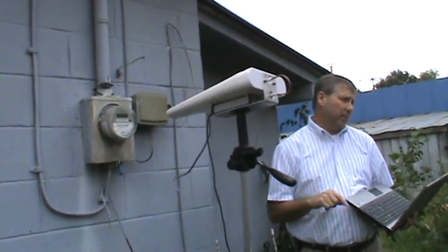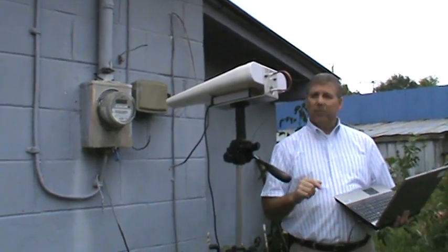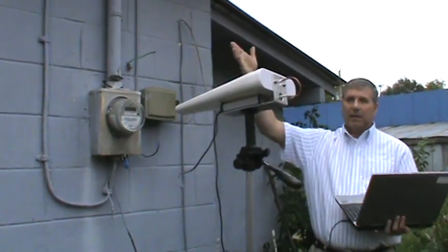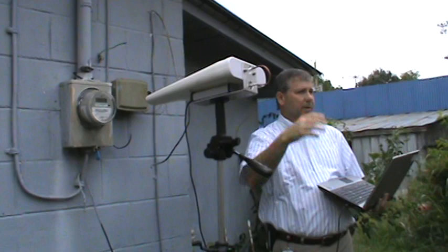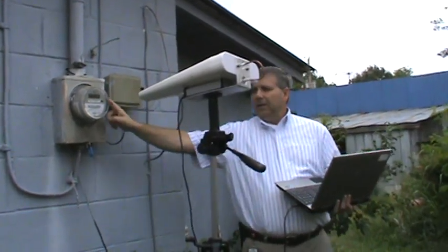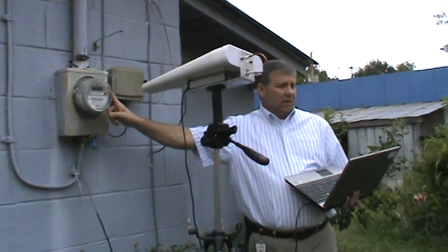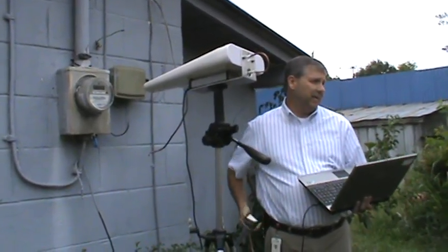Here at Southern Company, we chose a system from a company called Sensus FlexNet. It's a peer-to-peer, which means simply that this meter talks to the tower, wherever the tower may be. We really don't know where it's at. It could be anywhere up to 10 miles away from here. The other thing is with the mesh system, as I mentioned a while ago, they communicate continuously. Our meters only communicate 4 to 6 times a day.